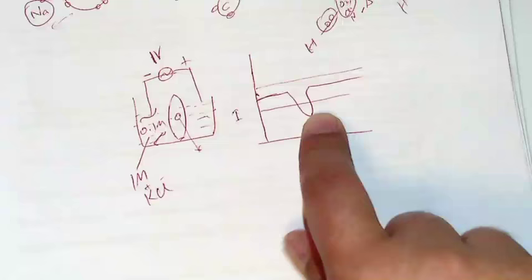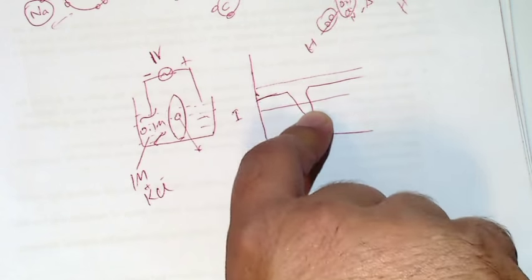If you don't put it inside a Faraday cage, if you don't put it on an isolation table, your noise is significantly fluctuating. And that noise comes from the equipment, like when it's moving, so a small movement can actually cause a big problem at the nanoscale. So it becomes very important when you're taking readings in nanoamperes or picoamperes. So I'm going back to our document camera. Basically you're expecting this kind of behavior, right?